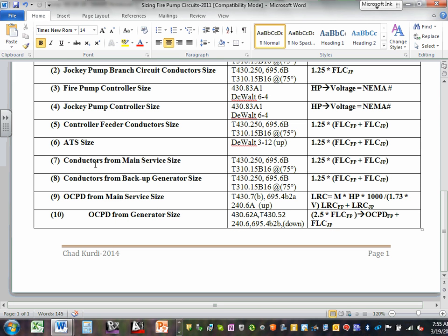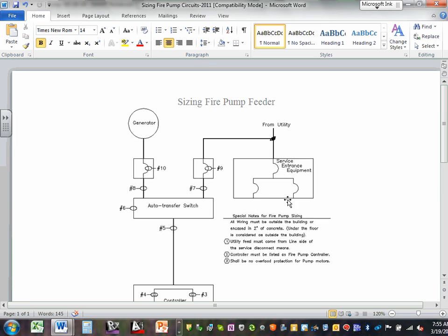Okay, let's go to 7. Conductor from the main service, conductor from the backup generator. How do you size them? Same thing: 1.25 times the sum of these 2 pumps. Everybody can see that? 1.25 times the sum of the 2 pumps. Very, very clear. Then we go to 9 and 10. 9 is the circuit breaker from the utility side. 10 is the circuit breaker from the generator side, because you have 2 sources.